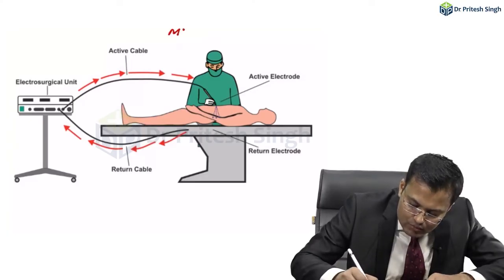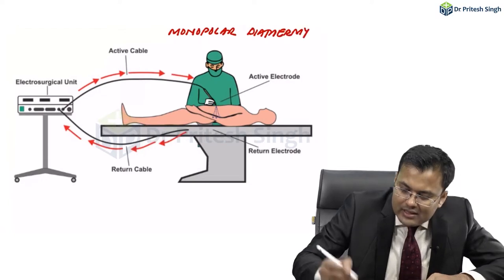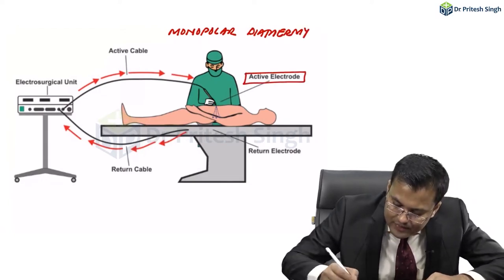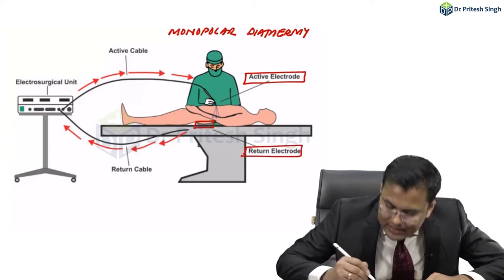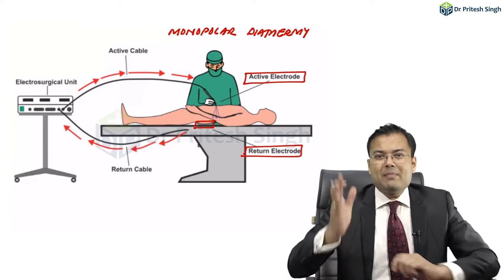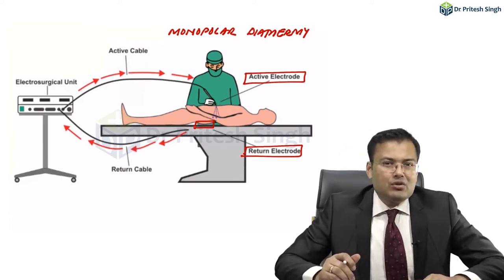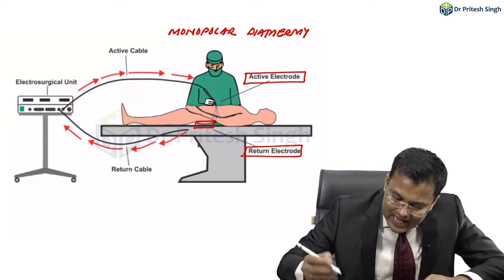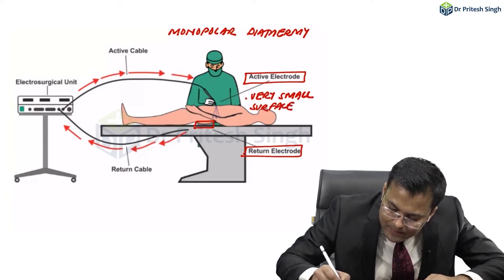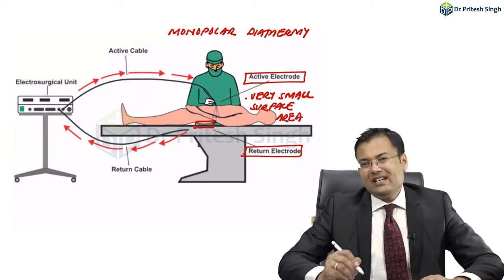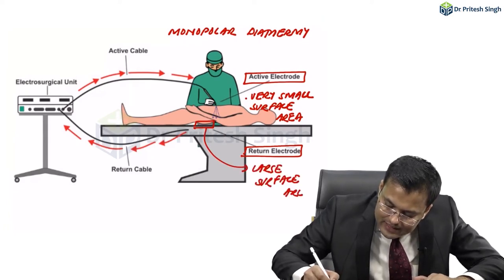This is how monopolar diathermy works. There is one active electrode and this is the passive or return electrode. You have seen in OTs we apply cautery pad, that is the return electrode or passive electrode. This active electrode has a very small surface area compared to the return electrode. The return electrode has a large surface area.